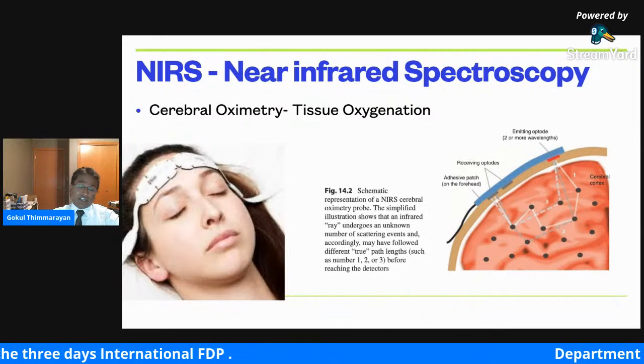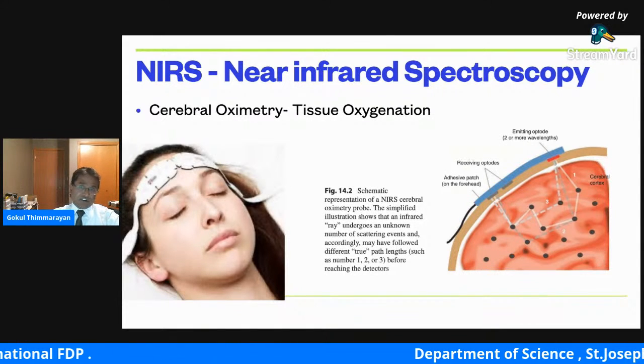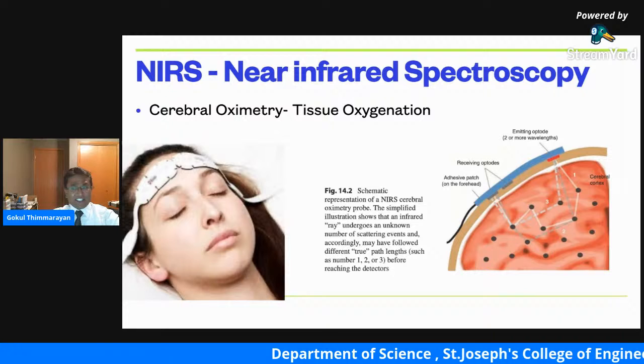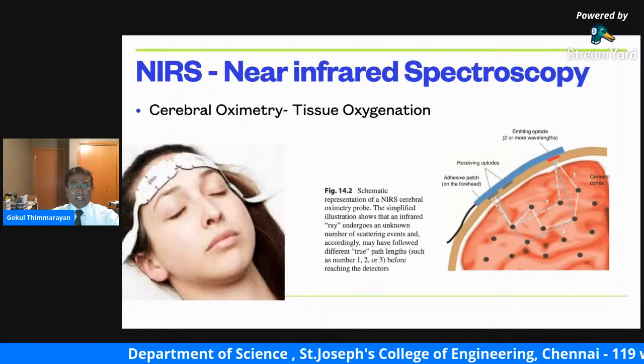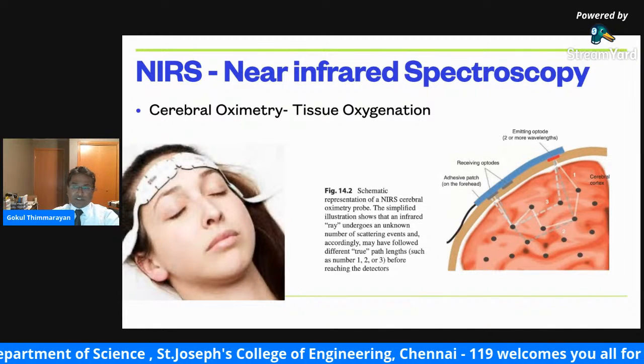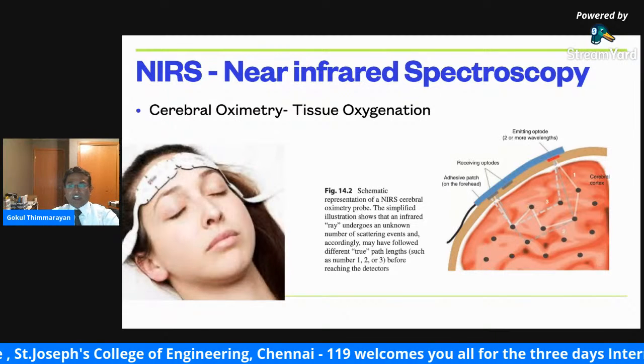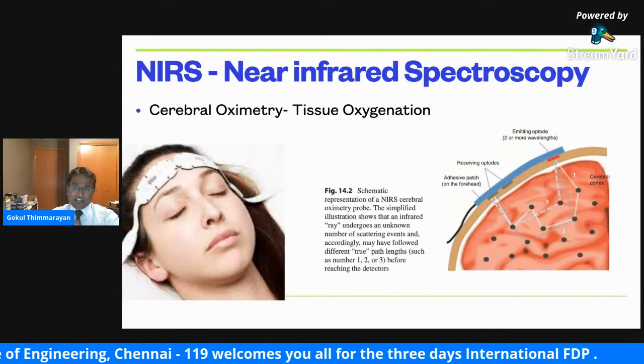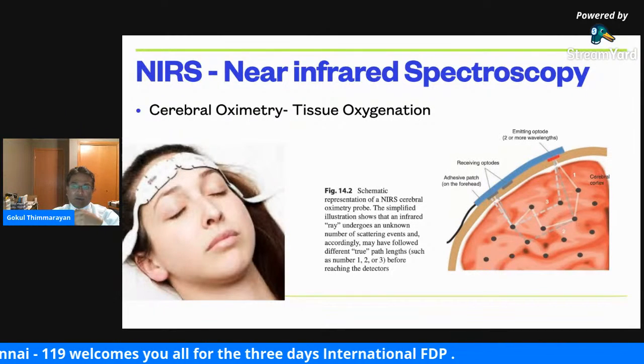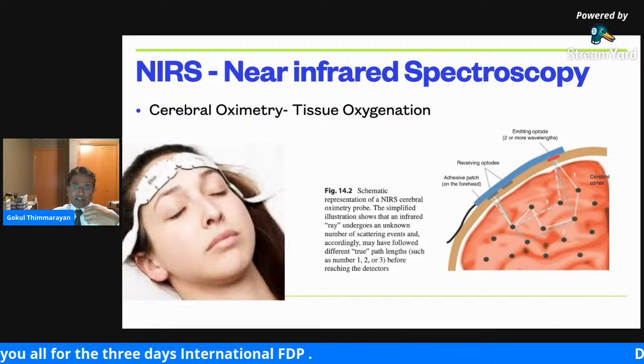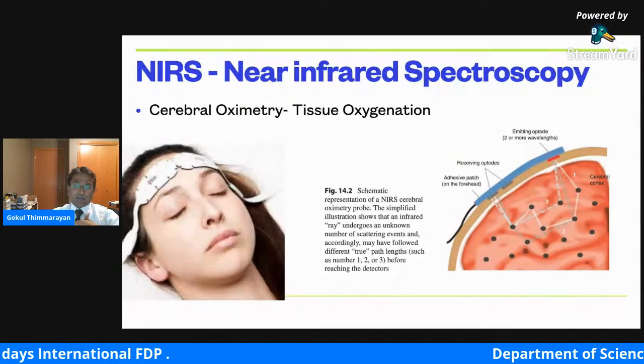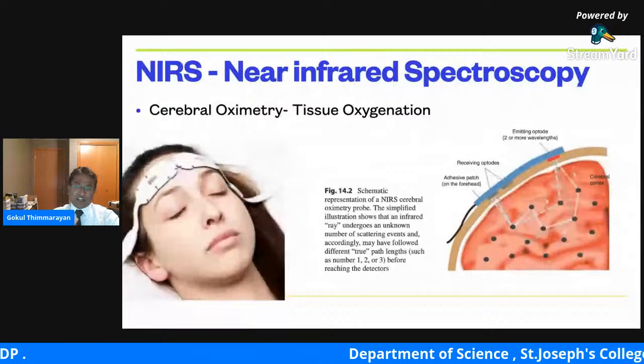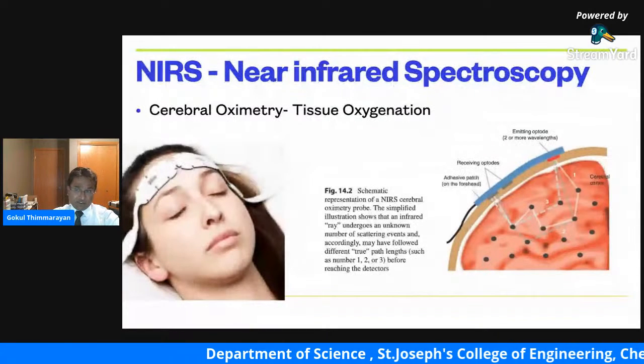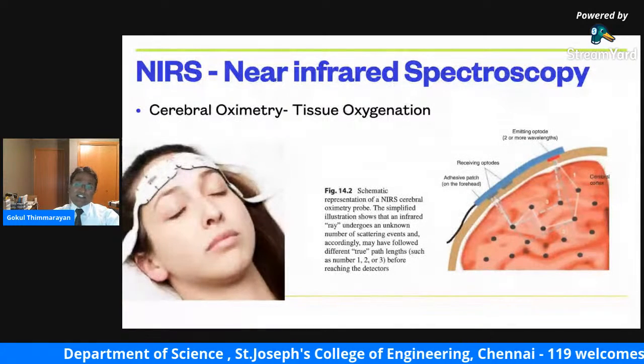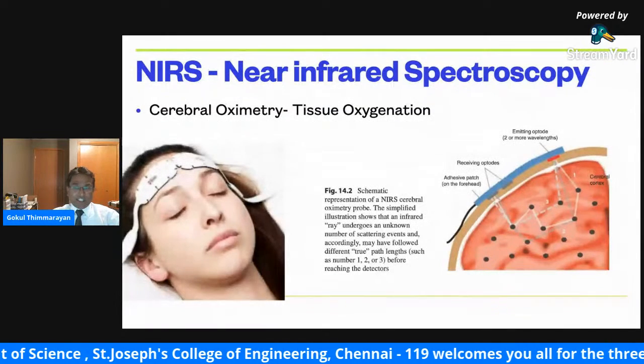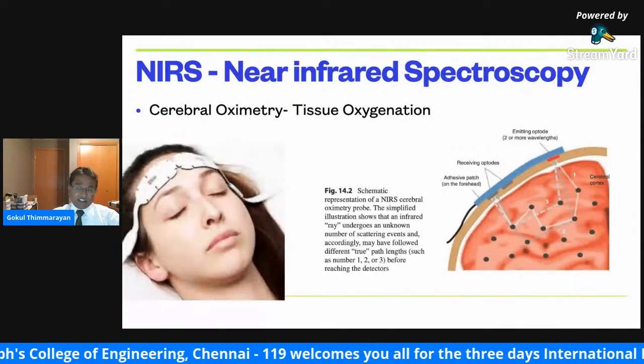could be assessed with near infrared spectroscopy, which is essentially the same as the pulse oximeter. At the top of the picture we could see a mention of emitting optodes, which are the light source, where it emits light and it passes through the skin, skull, and goes through the brain tissues. Unlike in the pulse oximeter, where the sensor is placed right opposite the light emitting source, here the sensor is placed distally. So the sensor detects the scattered light.